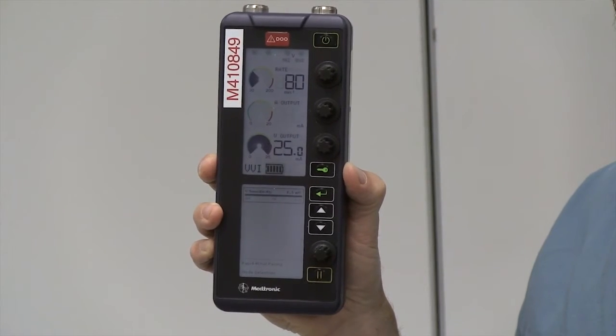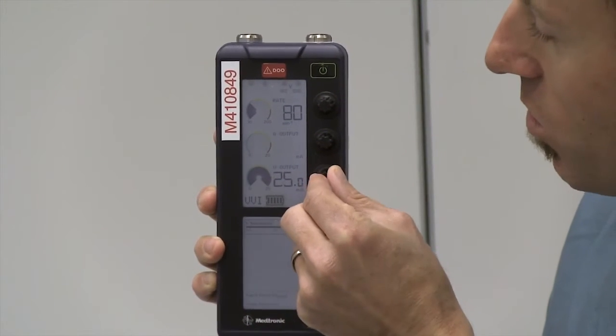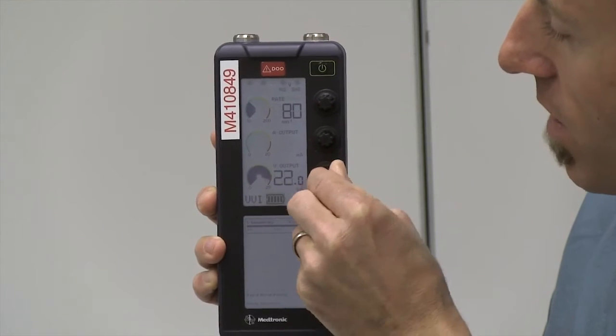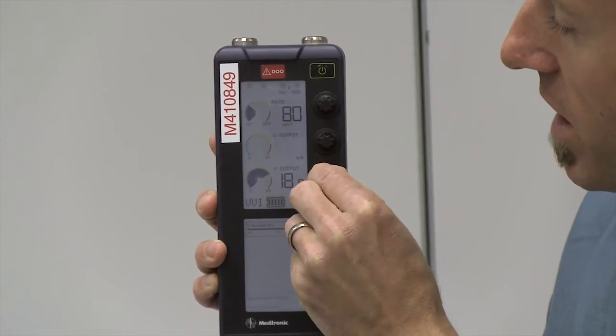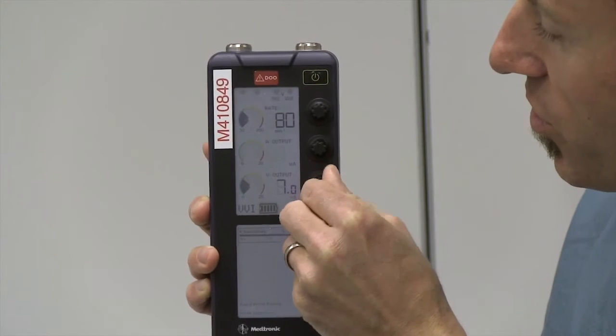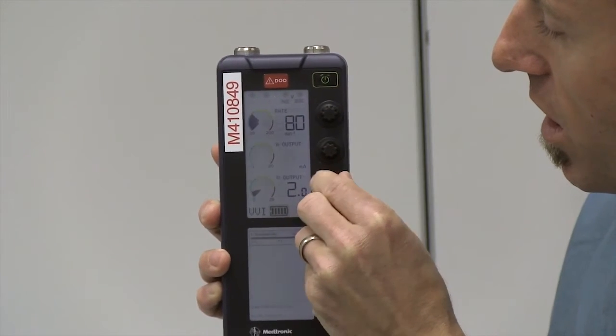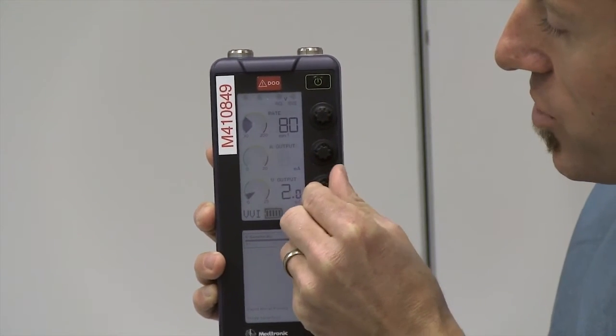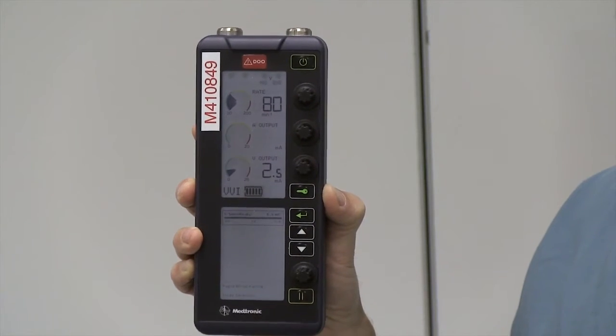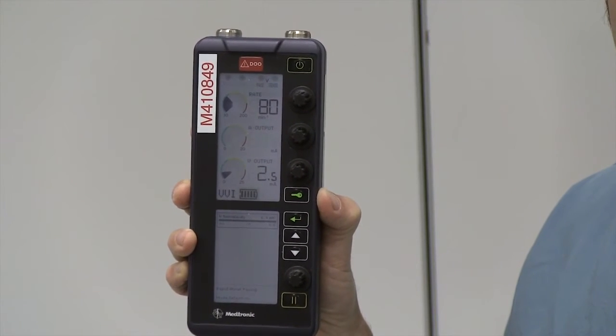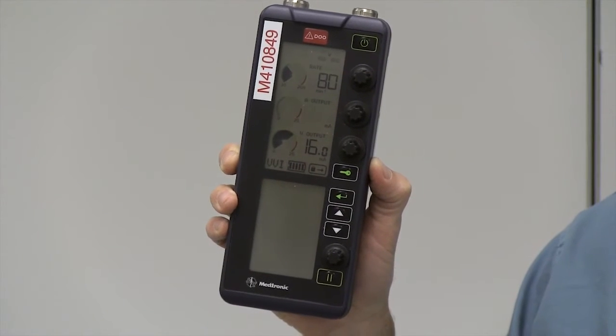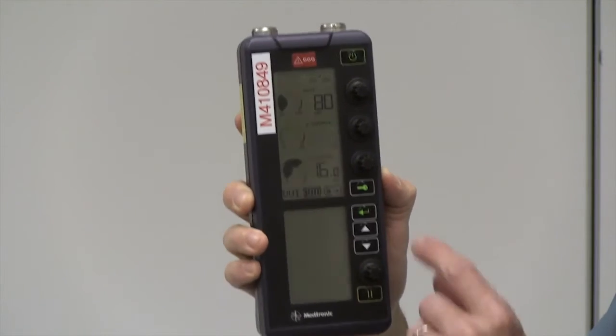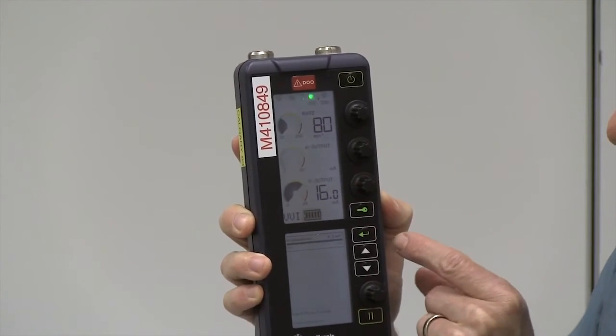Once you've attained ventricular capture on the pacemaker, you want to slowly decrease your output or your MA. You want to decrease the MA until you lose capture, and then 2 clicks higher, and leave the output at that particular point. If you have not made any adjustments to the pacemaker generator in approximately 30 seconds, the machine will lock at its current settings. To unlock it again, you need to press the lock key, and then you're back to where you were.